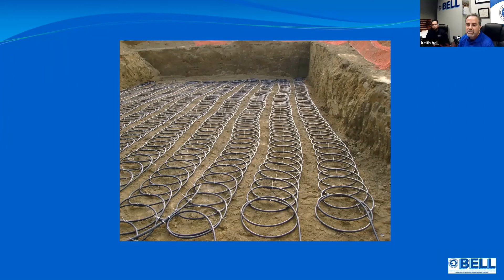And this is an example of those black pipes that go out to the heat, down to the ground. These are like the condenser units. So this is a split geothermal system. What these boxes are is essentially the same as your air conditioning unit that's out in your yard. With the geo system, we now put them in your basement. And up in the attic, typically, is where the air handler is that these feed refrigerant pipes to. So it's similar to our AC system, but your condenser's inside. That's another benefit with geo. The units aren't out in the weather. They tend to last longer because you're not exposed to the weather, and you don't have any condensers on the outside of the house.